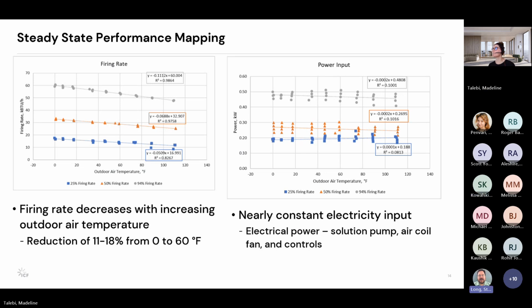One additional follow-up on that question is, as I recall, on each of those at the baseline, they actually commissioned the unit. I don't recall, Madeline, but they compared against the manufacturer's stated specs, and I think it pretty well lined up. But I do think they forced the system to run at different firing rates just to perform the test matrix that was asked for. Very good. That makes sense, Stephen. Thank you.